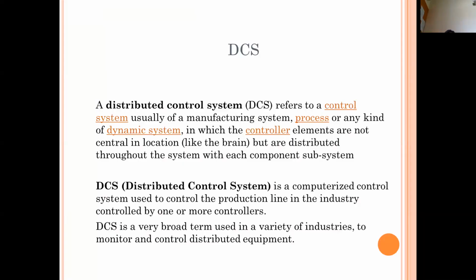Okay, coming to the DCS, the distributed control system. Most viewers will say that the DCS is a higher technology of the PLC, but I don't quite agree, because the DCS is better at handling analog things, whereas the PLC is better at handling discrete things. The major difference between the PLC and the DCS is the scan time.